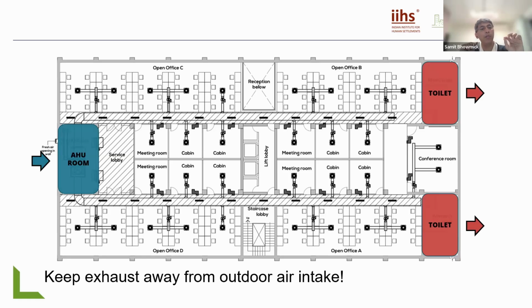We need to make sure nothing else is contaminating the fresh air getting into the space. So placement of outdoor air intakes and extraction fans, making sure extraction is effective, should be the number one most effective way of improving indoor air quality. ASHRAE gives us a formula for how much should be done, but in actual practice, what really works is looking at these small things - locating the service rooms right, making sure extraction works well. That's the most important thing to look for.